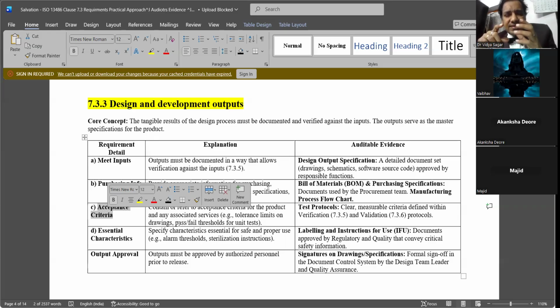There will be a few things which are essential, but really won't have much impact or effect on the risk or performance of the device. That you can look at when you are doing the risk management file, because the risk management file is always integrated with design and development. That time you have to look into the risk. This has not met the design inputs. The output has not met the inputs. So what is the risk it is carrying? Or should we also modify this? If I modify this, will there be an effect on other parameters directly linked to device performance or intended use? Or can I just work on this? It will be really interesting. Which one to touch, which one not to touch, which one has to come close.